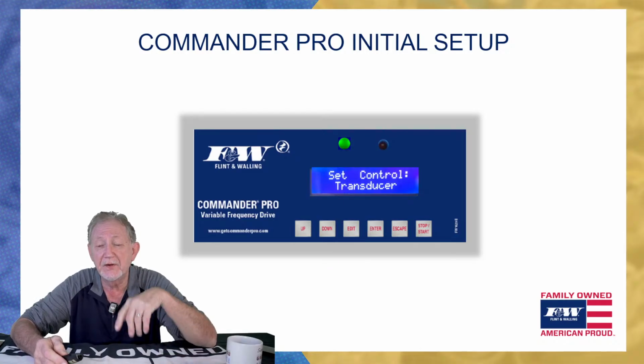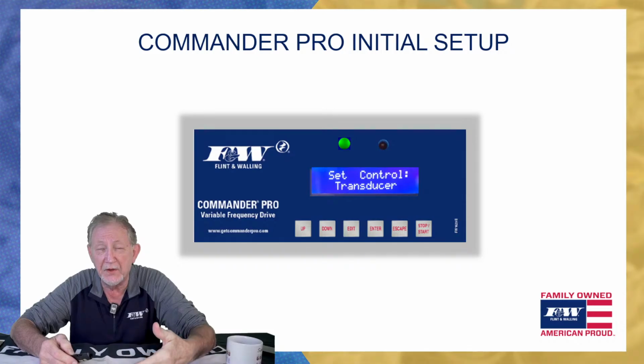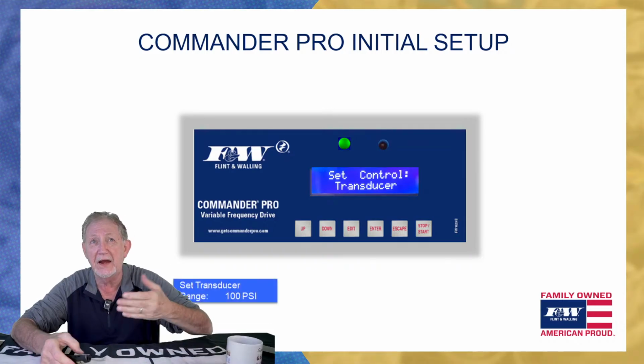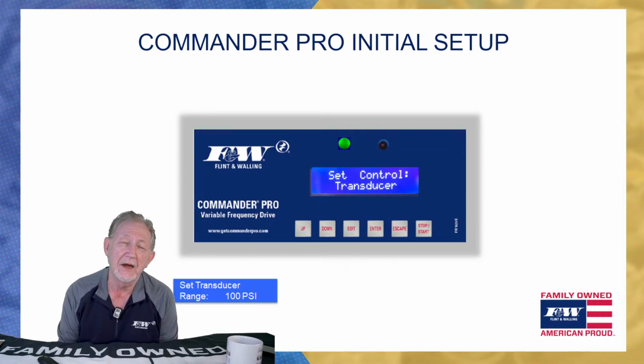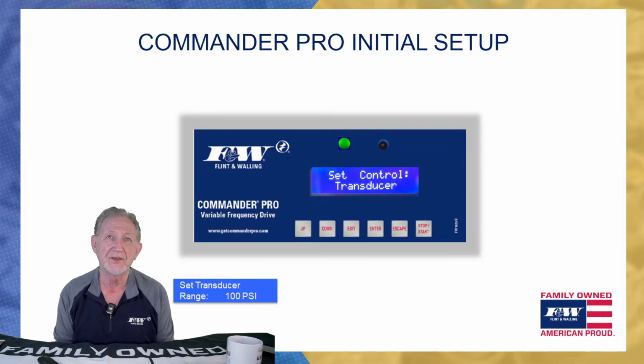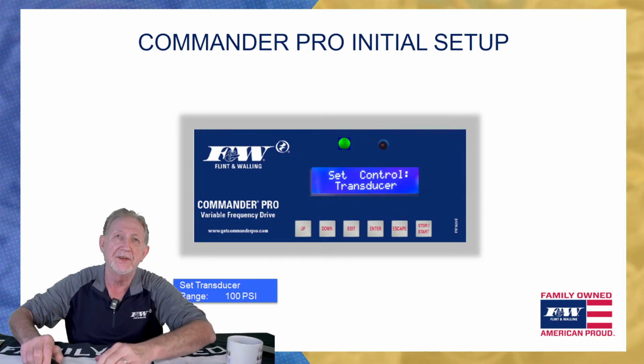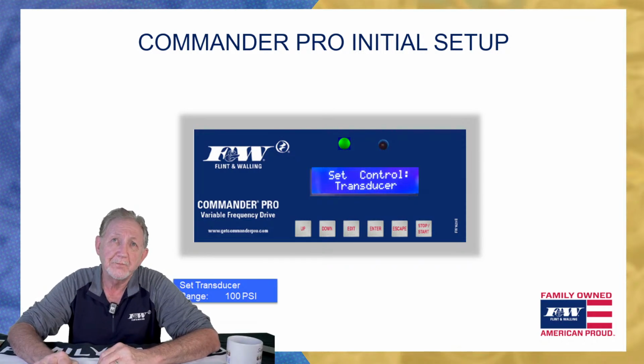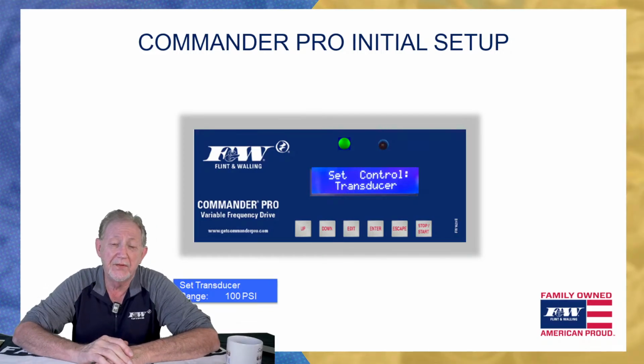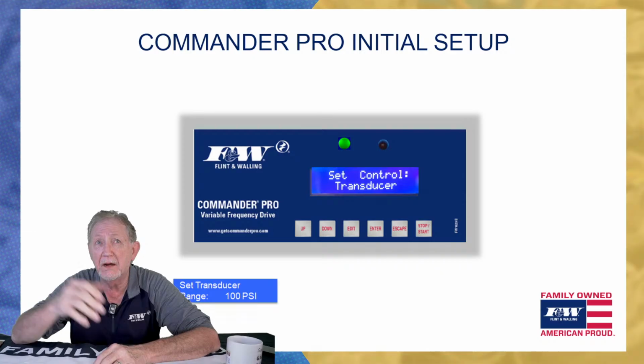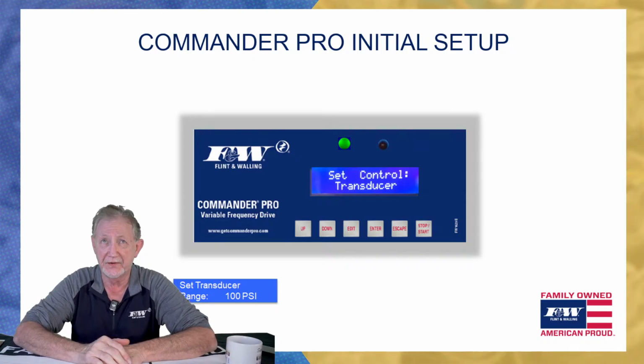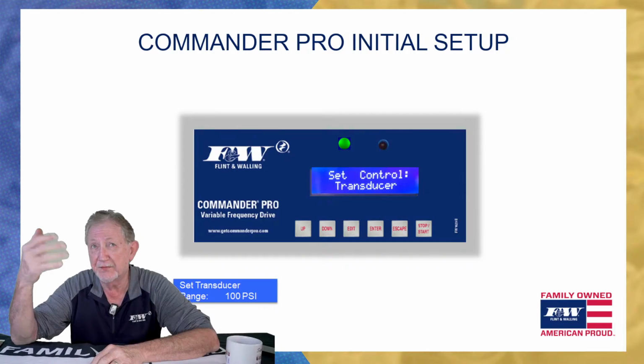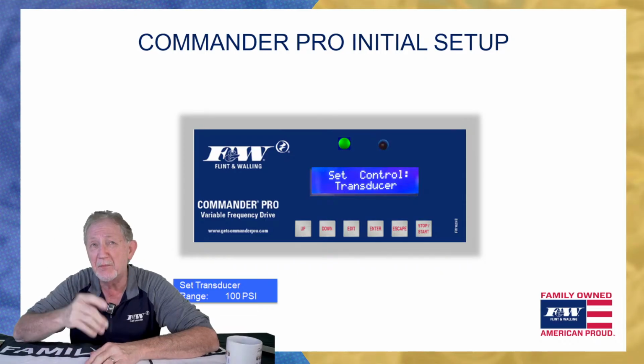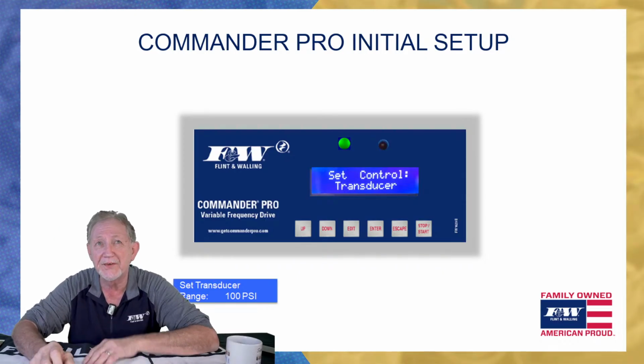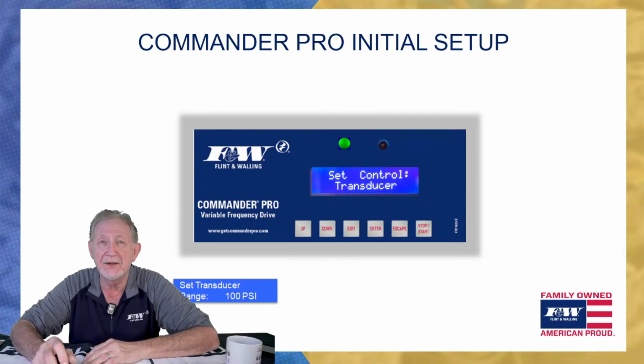When you select that transducer, what's going to happen is you're going to have a sub-menu now come up. And there's going to be three things there. All right, here they are. The first thing is it's going to say, well, what's the pressure range of that transducer? You probably won't have to change this at all because this is going to be factory set at 100 psi. And that's what we send out with these drives. Now there are larger transducers, higher psi transducers available. If it were a 150 or 300 pound transducer, here's where you would make that change. In that menu, you would move that from 100 psi up to whatever that range is on that transducer.